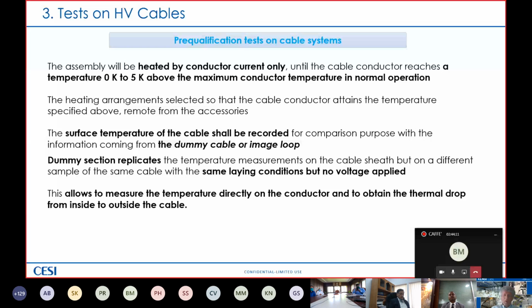Talking about the pre-qualification test, the assembly will be heated by the conductor current only until the cable conductor reaches a temperature of 0 to 5 centigrades above the maximum conductor temperature in normal operation. For example, for XLPE, we're talking about 90 degrees, but can be also lower. The heating arrangement is selected so that the cable conductor attains a temperature specified above, remote from the accessory. So this measurement, the heating arrangement should be remote from the accessory.